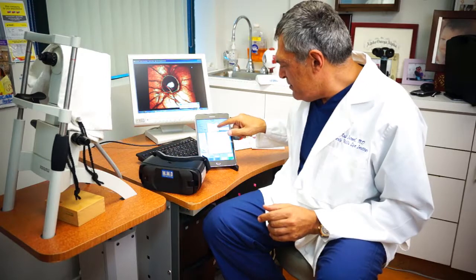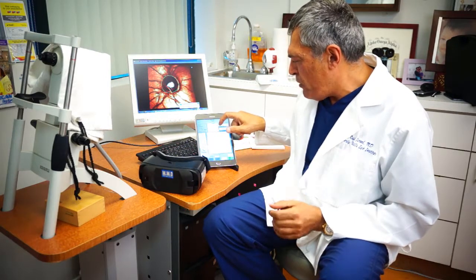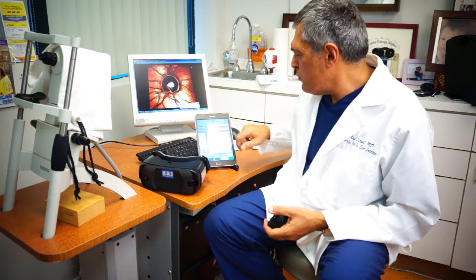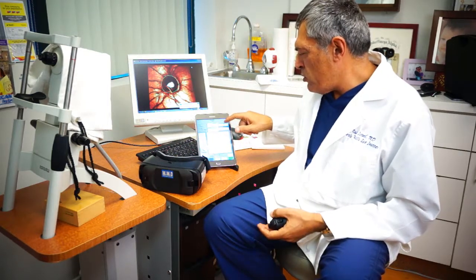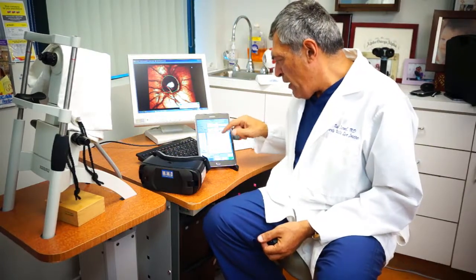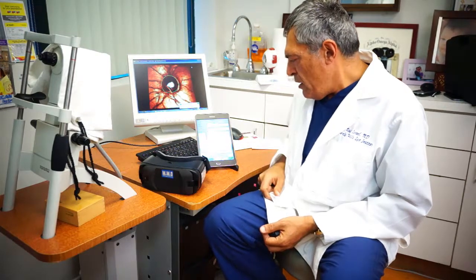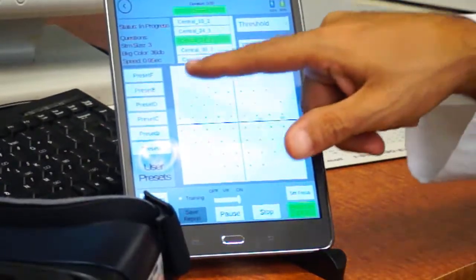You select the pattern and the patterns are 10-2, 24-1, 24-2, 30-1, 30-2. So I usually like to do a 24-2. I like to do a threshold test and this will do an interactive fast threshold test. So at this point you press the start and the controller will now program the virtual reality goggle the correct test pattern. Here is the test pattern.